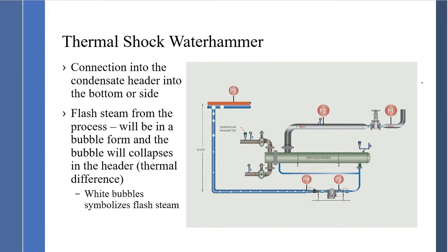In process P1, we might be supplying 150 PSI steam at 366 degrees to the process. At P2, pressure is reduced to 100 PSI or 338 degrees. The condensate comes down to the steam trap at 338 degrees at P3, then passes through a pressure reduction through the steam trap to a lower pressure at P4 in the condensate system.